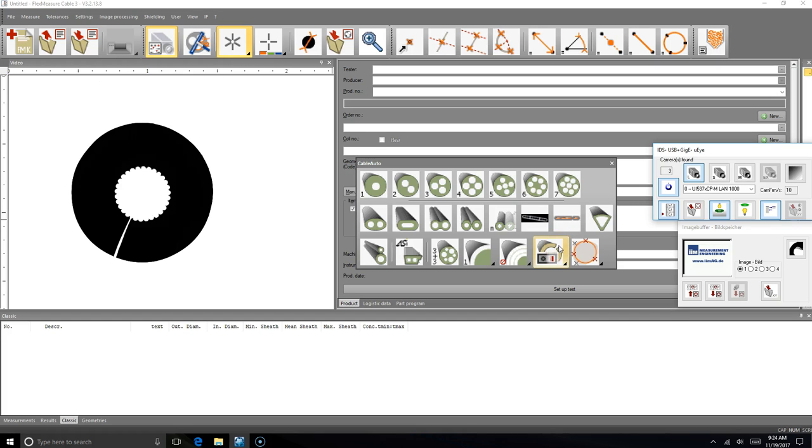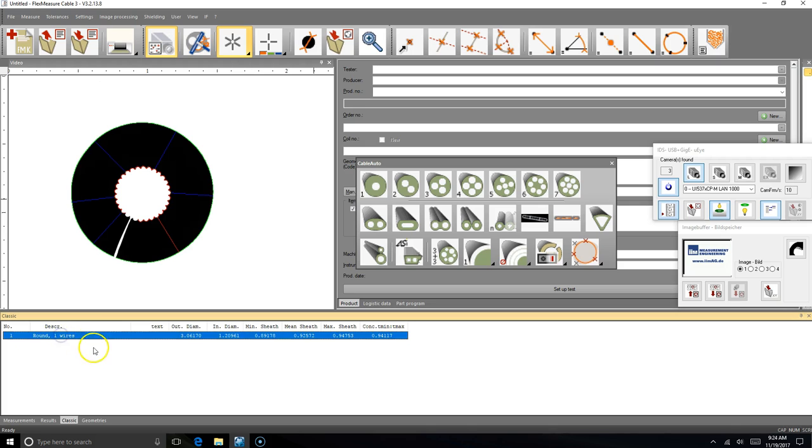I'm going to kind of walk through these backwards. I'm going to show one more thing on this, and we're going to walk through backwards. So in this case, if we want to just measure from here to here, it is just a single conductor with 1 layer. If you want to take a measurement on that, all we have to do is push go on this icon, and it takes a few seconds, maybe, and it shows you the actual values down here in the bottom.